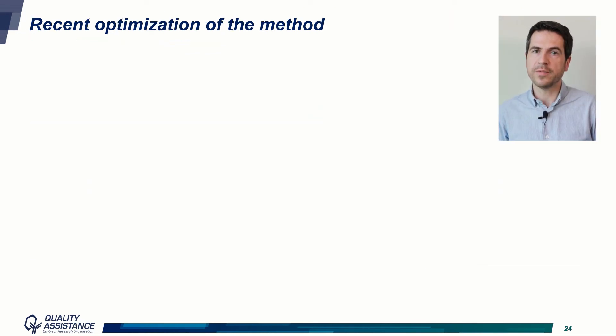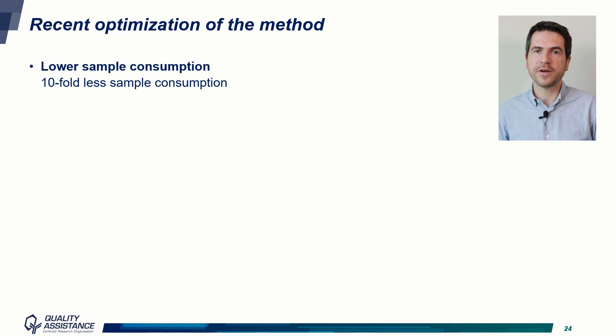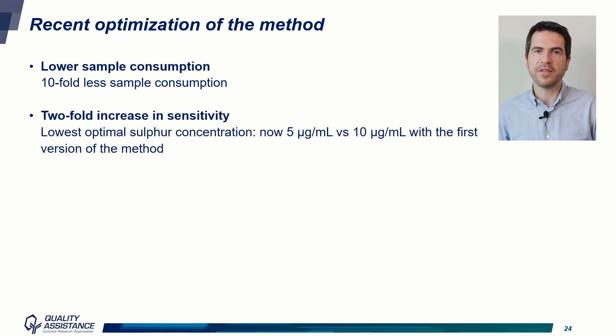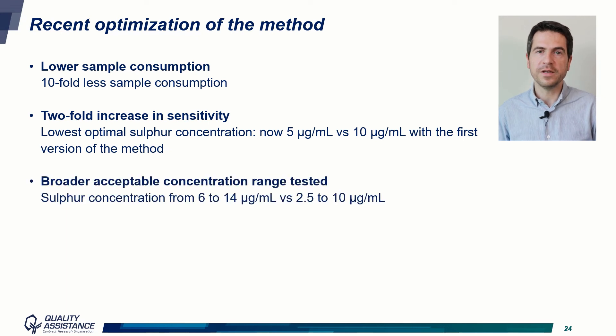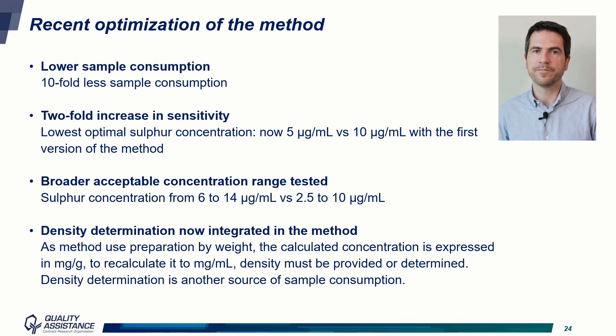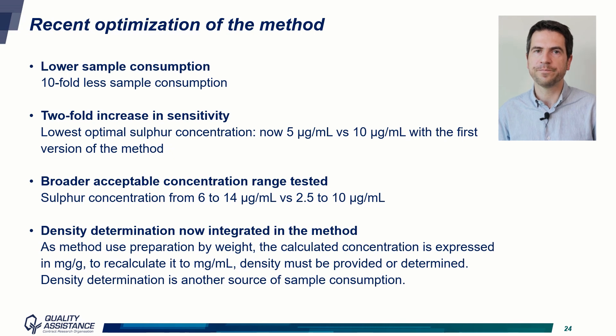We have now been using the method routinely for some time. On top of the added value to our customers, we noticed that another challenge was the sample amount needed. Therefore, we optimized the method: we decreased sample consumption by a factor of 10, increased the sensitivity of the method with a two-fold decrease of the optimal sulfur concentration, and the range of the method is now broader. Finally, we included the determination of sample density directly in the method. As the sulfur concentration is measured in mg per gram, sample density must be known to convert the result to mg per mL. In the previous version this had to be determined independently, but in the new version it is included within the method. This development is now complete and will shortly be made available to our customers.